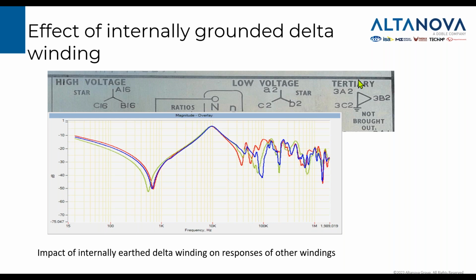And our experience shows that when there is an internally grounded tertiary winding in one corner, it quite often makes a mess with the traces measured on the other two coils, normally higher on the coils which are closer to the tertiary windings on the columns. So this is what we measured this time as well, and this is what you should be aware of.